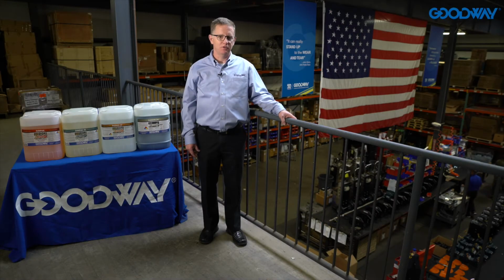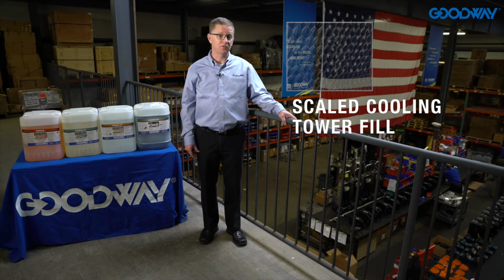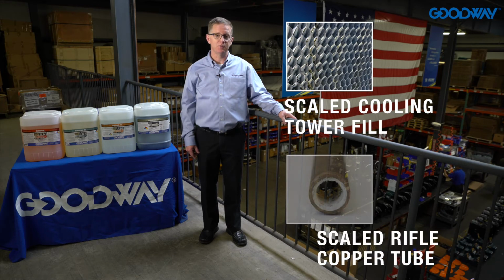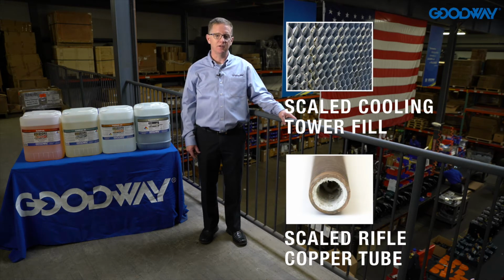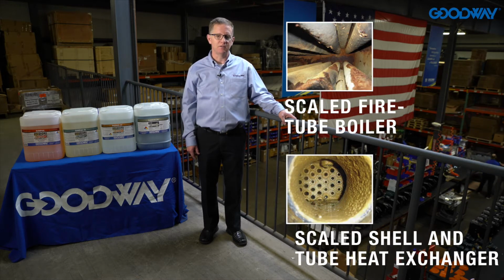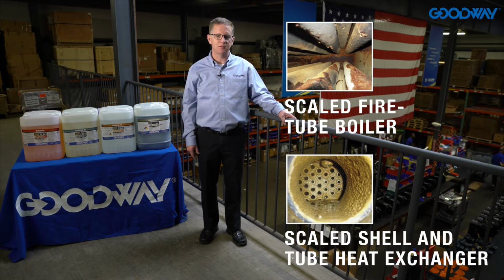Not in most applications. In certain situations, such as a cooling tower, you'll be able to look at your fill material and see the scaling occurring there. If you have significant scaling within your cooling tower, there's a pretty good chance that you have it within the equipment that the tower is cooling as well.